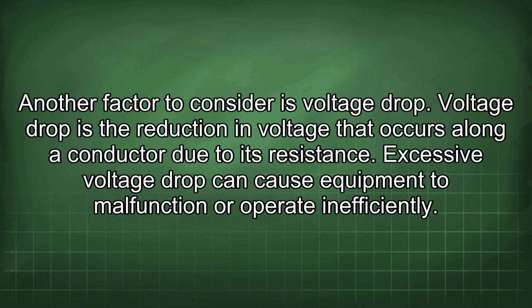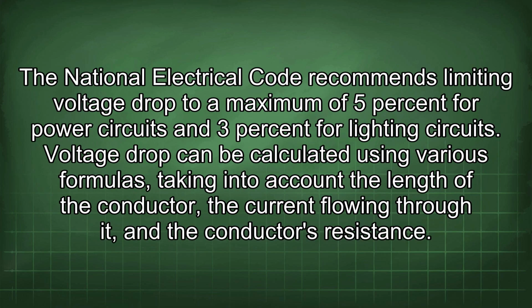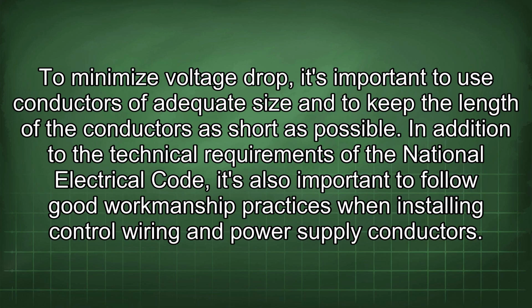Another factor to consider is voltage drop. Voltage drop is the reduction in voltage that occurs along a conductor due to its resistance. Excessive voltage drop can cause equipment to malfunction or operate inefficiently. The National Electrical Code recommends limiting voltage drop to a maximum of 5% for power circuits and 3% for lighting circuits. Voltage drop can be calculated using various formulas taking into account the length of the conductor, the current flowing through it, and the conductor's resistance.